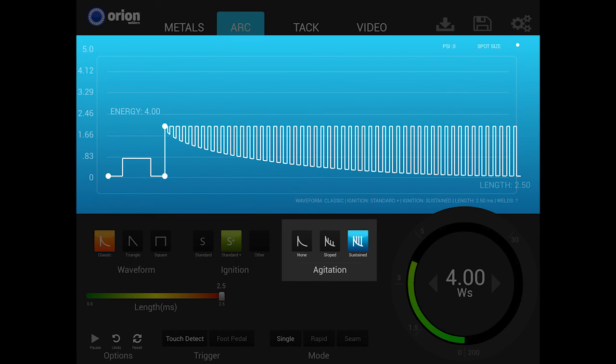The sustained option offers high levels of agitation for improved weld spot strength in some metals. The high levels of agitation energy will affect the spot size because of the extra energy used in this option. To compensate for this addition of agitation energy, it is recommended to lower the overall weld energy slightly when using this option.